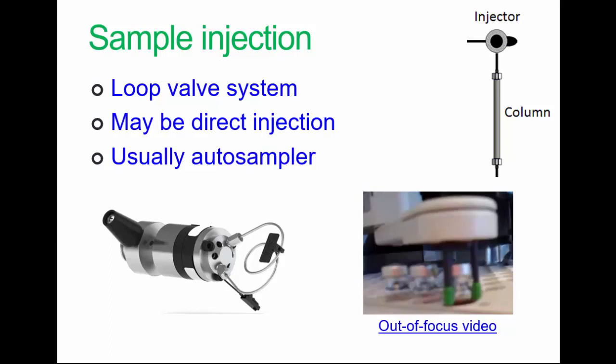Some systems still use injection from hypodermic into a loop valve system, where the loop is a very accurate measure of, say, 20 microliters. However, these days, most often an auto-sampler system is used, such as the example given in this somewhat out of focus and wobbly video. But I'm sure you'll get the point, so have a look at the video.